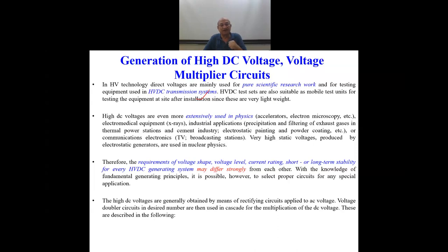And one very important thing you can imagine: when you apply DC to equipment, what do you test? You always test the insulation, the dielectric behavior. So when you apply DC to a capacitor, will there be any charging current? No, there won't be any charging current. So the power drawn by the test apparatus is very small. The voltage has to be of the required magnitude, but the current drawn by the test apparatus is very, very small. So when the current reduces, the size of the DC test set also reduces considerably. Then you need DC.